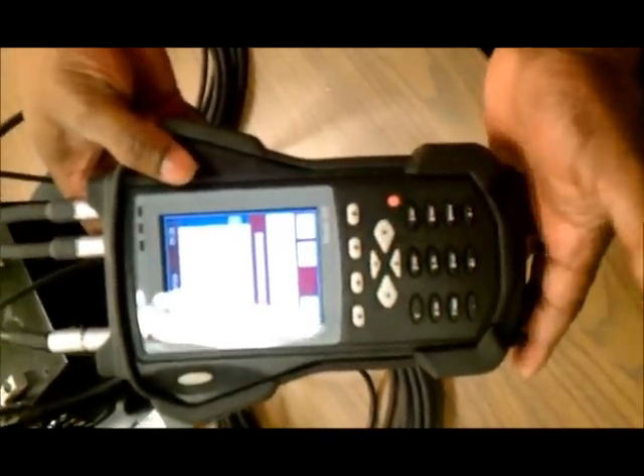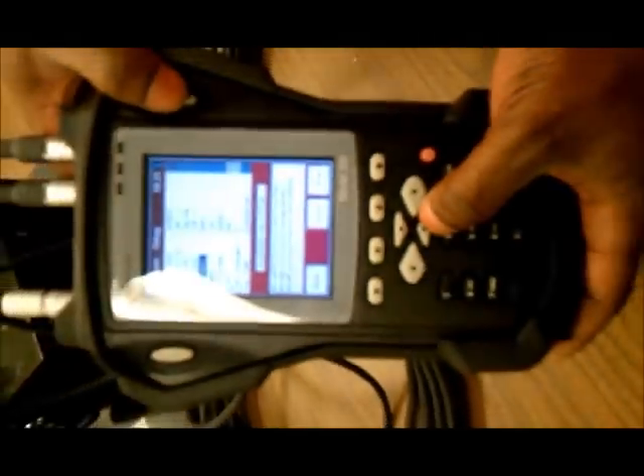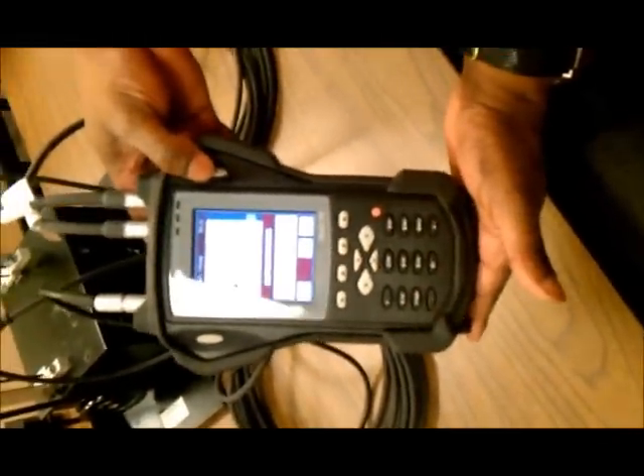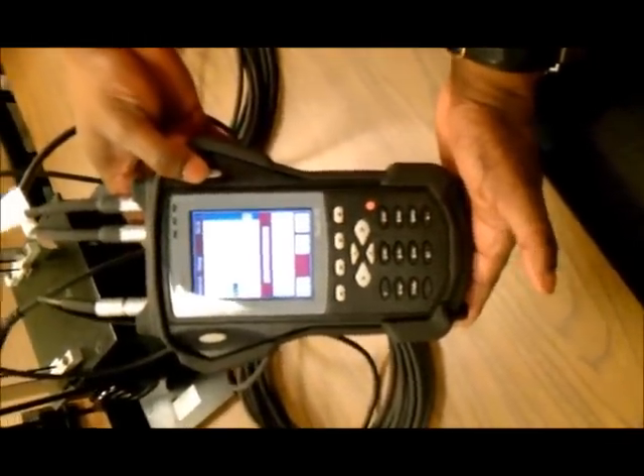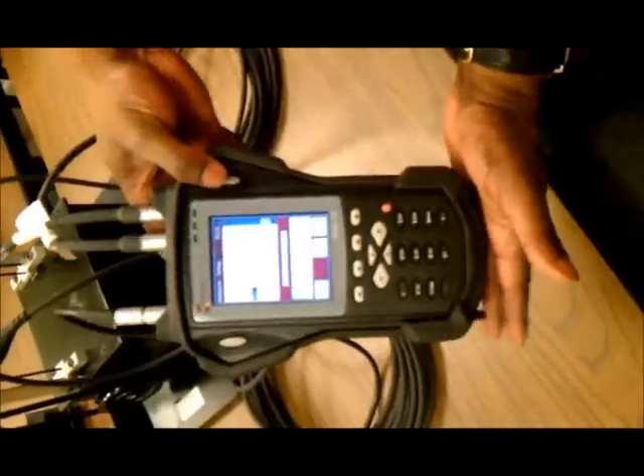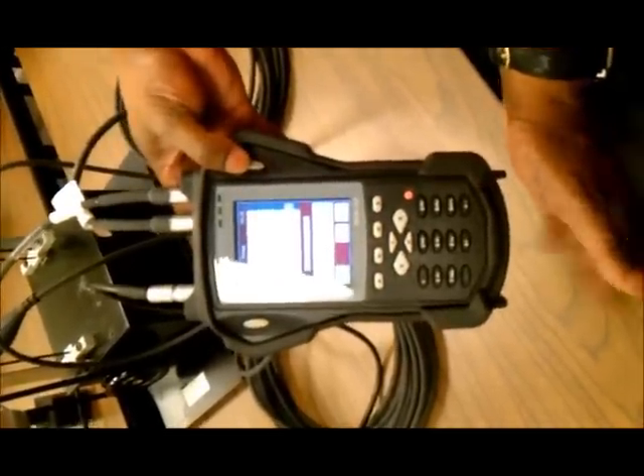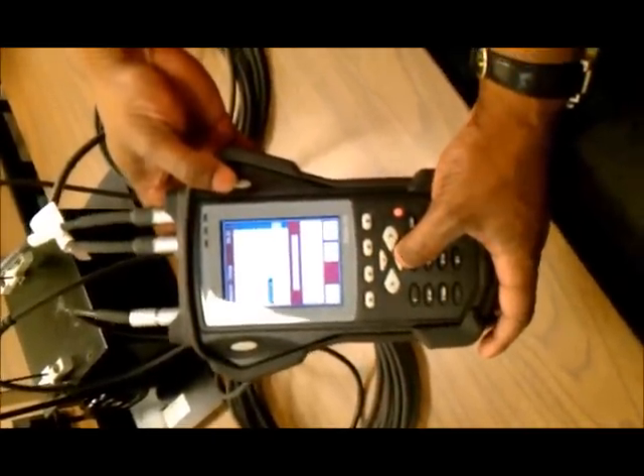Also, we have the ability to set up our X units, either in Hertz or CPM. For this example, we'll use CPM. And then we have the detection type: root mean square, peak, peak to peak, true peak, and true peak to peak. So we'll go ahead and pick our peak to peak. And we have the ability to set a high pass filter to filter out noise that we don't want, that we don't care about. We'll leave that at 2 hertz.